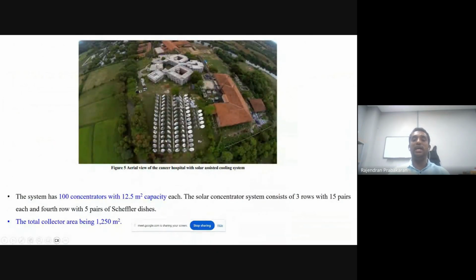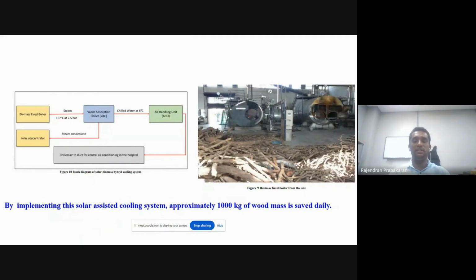We can see this is the aerial view of the solar collector areas. Totally 100 concentrators have been used with a total area of 12.5 meters square each. Totally 3 rows with 15 pairs were used, and the 4th row has only 5 pairs. So the total collector area is about 1,250 square meters. With this energy, they reduced the necessity of wood by about 1,000 kgs daily. So this is also effective in reducing the emissions from biomass burning.